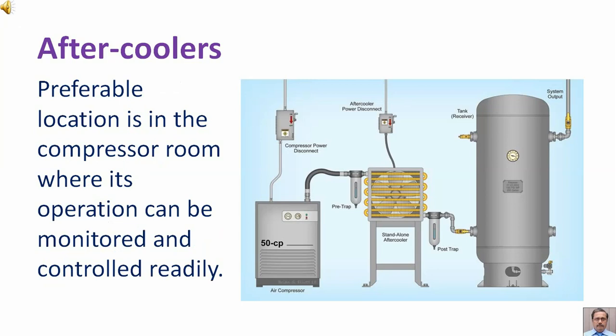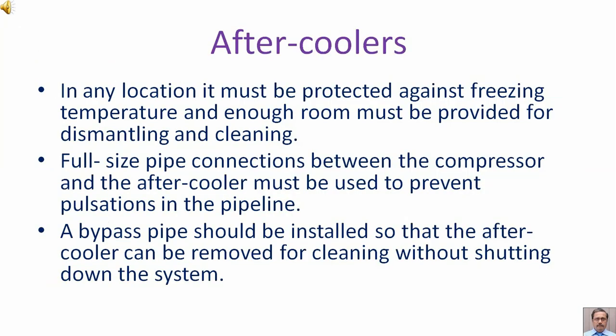The preferable location is in the compressor room where its operation can be monitored and controlled readily. In any location it must be protected against freezing temperature and enough room must be provided for dismantling and cleaning. Full-size pipe connections between the compressor and the aftercooler must be used to prevent pulsations in the pipeline. A bypass pipe should be installed so that the aftercooler can be removed for cleaning without shutting down the system.